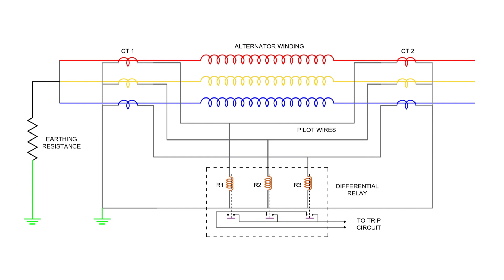Under normal conditions, the secondary currents cancel each other out, so no current flows through the relay coils. But when a fault happens, this balance is disturbed. The difference in current flows through the relay coils, which then activate the tripping mechanism to isolate the alternator.